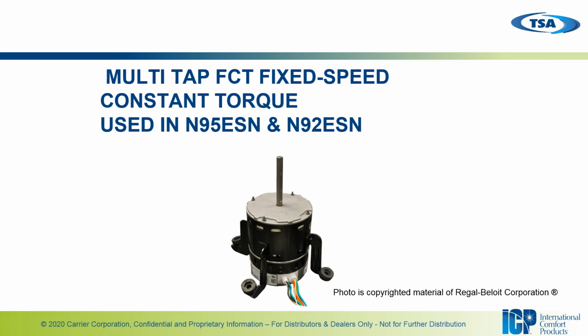And finally, we're going to talk about the fixed speed constant torque motor, otherwise known in the industry as the X13 motor. All right, this is probably the most common motor we have out there. You're going to see these in the majority of the single stage furnaces. This, guys, is taking the place, or has taken the place, of PSC motors. So this is the new standard in high efficiency gas furnaces, as well as standard efficiency gas furnaces, ever since July of 2019.